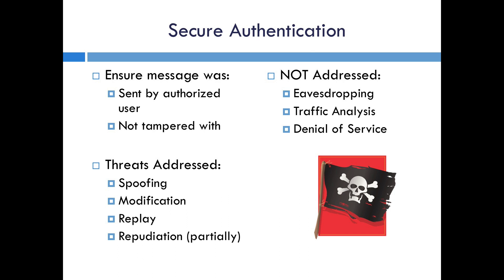Secure authentication is basically trying to prevent spoofing, where you could pretend to be the real master. It makes sure you can't modify a message and change it, like changing a read into a control, or changing a point that's going to be acted on in a control message. It also makes sure that you can't replay a message — you can't record what a control message looks like and then send that same control a week or a few days later.